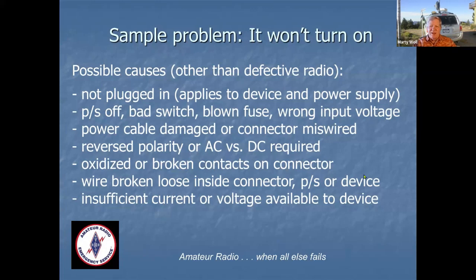Insufficient current or voltage: I went to visit a Boy Scout camp where they had a VHF radio up in the mountains, and he said every time he hit transmit, everything turns off. We obviously suspected the supply, and I took a look. This was a typical 50 watt mobile, which normally draws around 10 amps or so, and he was running it from an Astron 10 amp supply. He didn't realize that 10 amps is the peak rating on those supplies, not the continuous rating.